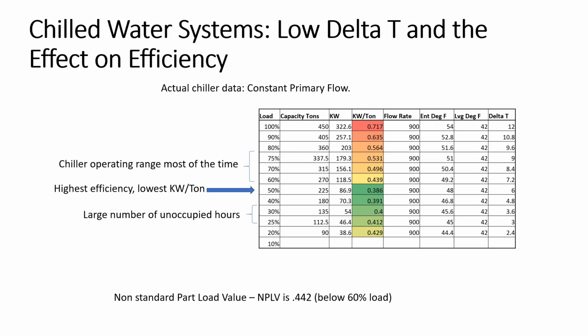It's rare that you get to 100%. And in this case, the client said, yes, on Monday morning we might load up, and then it'll run like that for a couple of hours. So you're not at its most inefficient point. It's where it's running most of the time that you need to get the best efficiency. And in this case, 50% is its best efficiency, but you're running most of the time at 60% to 75%.